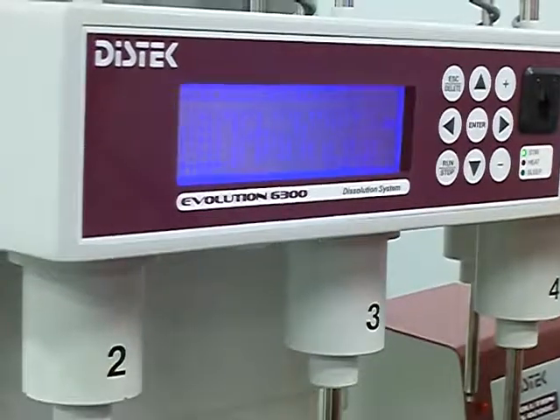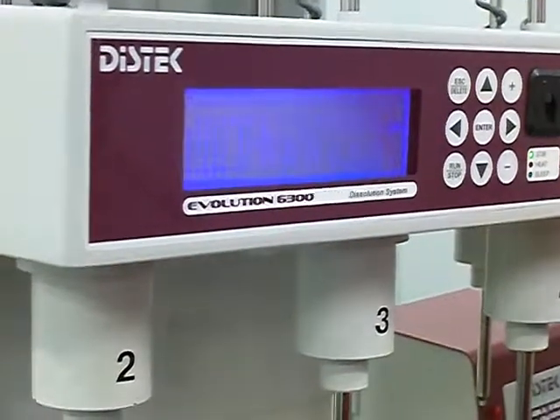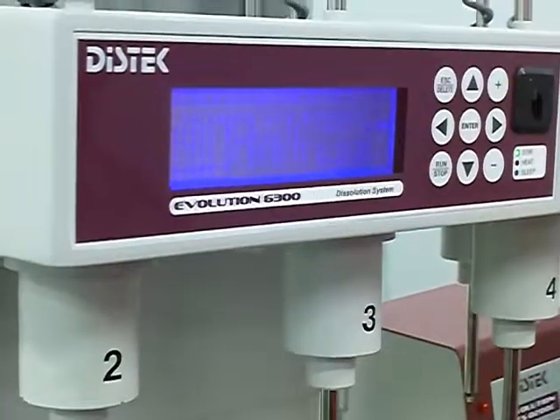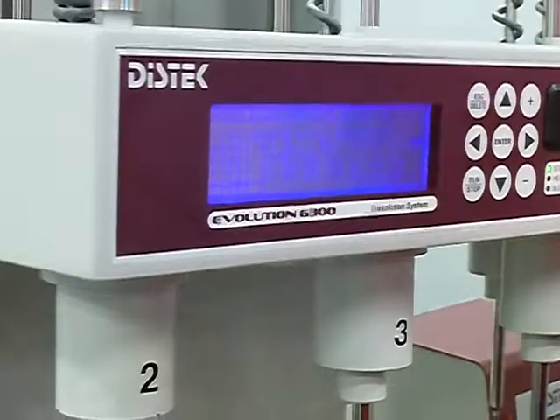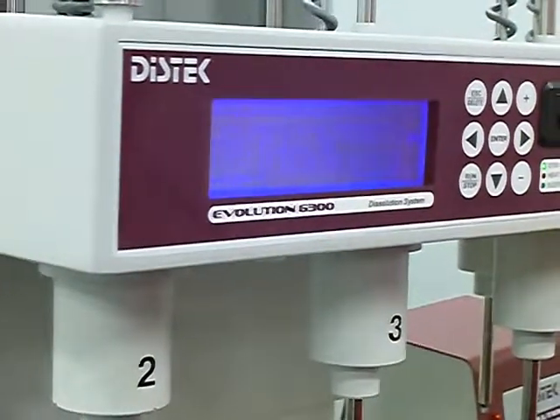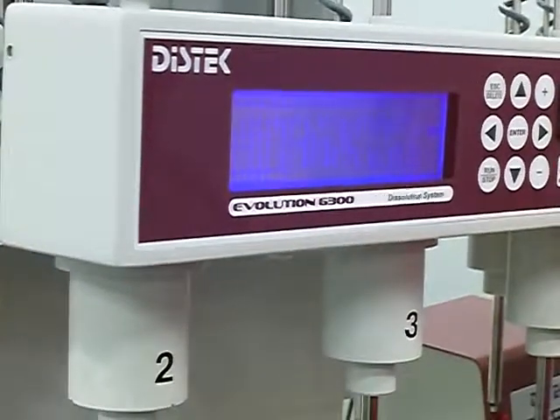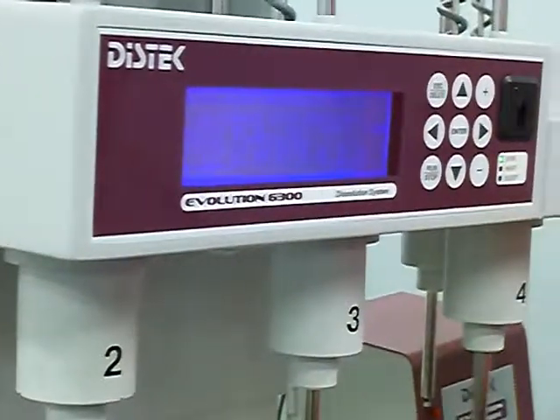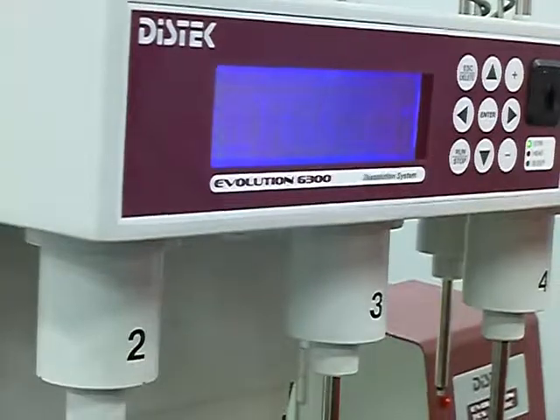I typically will do the low calibration first, and then of course heat everything back up. The low calibration needs to be about 20 degrees or less Celsius. And then the upper degrees needs to be 37 degrees or more. I typically try to get about 40. So I try to do the first one at lower than 20 and the other one at around 40 degrees.